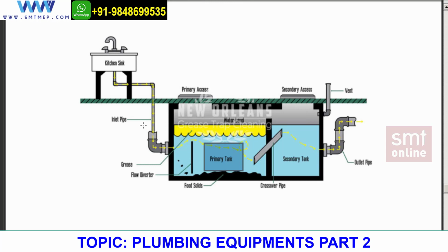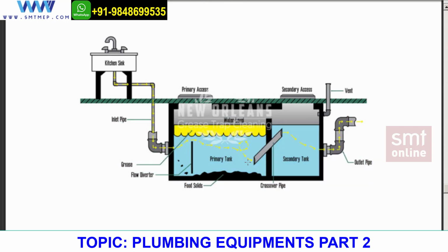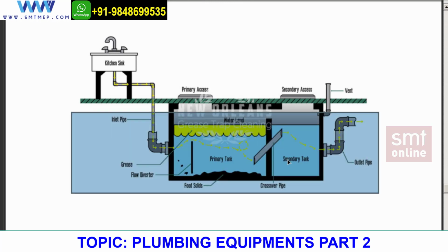And that old water is what? It is cooled down. The moment it is cooled down, as you can see, this yellow color grease or oil has separated because it is cooled now. So this is heat transfer taking place over here. It goes on. Once it is done, the water is separated from the oil and grease. It is floating, and the food particles also. And only the water will be sucked by this pipe.